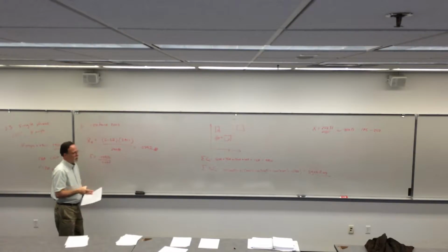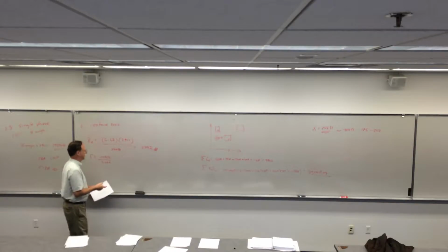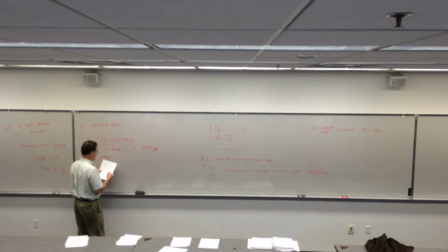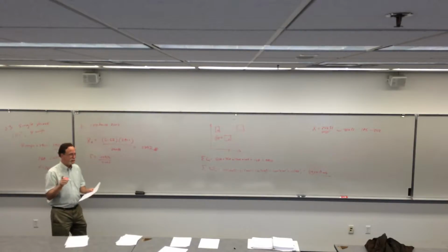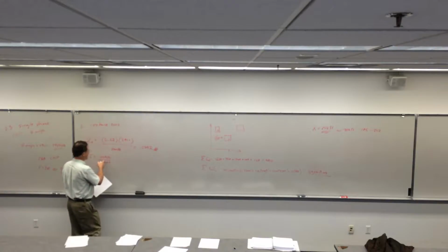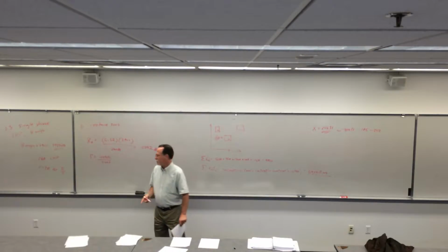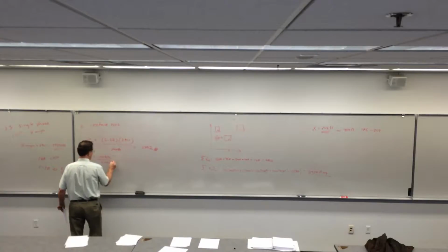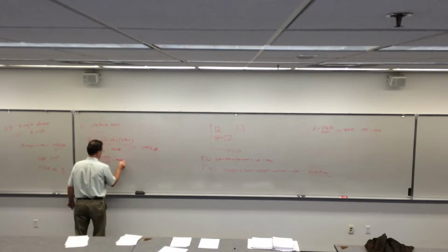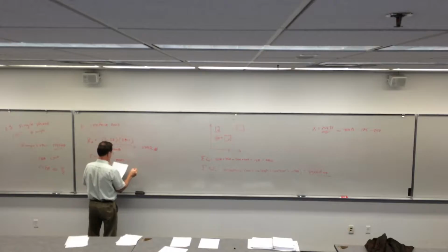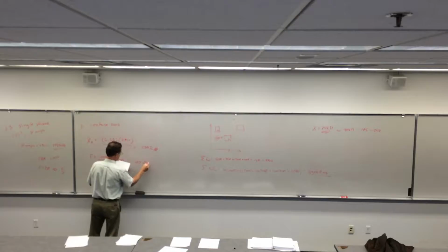Now I go in here and put it on resistance per 1,000 feet. Okay, great. Skip a step. I skipped one unit on here. Look what it cost me. Now let that be a lesson. Write your units down. Okay, 0.024 ohms divided by 224 feet. What is the table? It has resistance per 1,000 feet. So if I've got resistance per foot, I multiply by 1,000 feet. And I end up with the grand total of 0.107 ohms per 1,000 feet, which is the table.